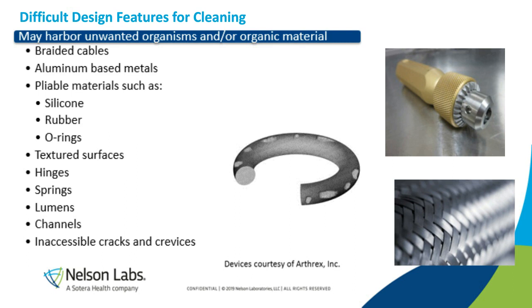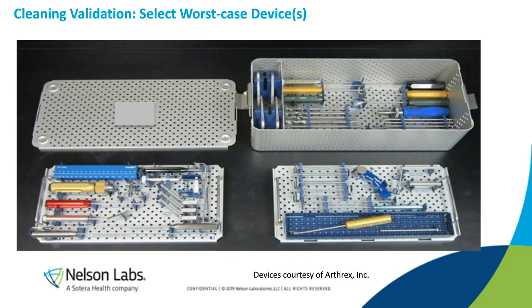Here's an example of how we would choose a worst-case device for a cleaning validation. As you can see, this tray of devices will be used for the same surgical procedure. And now we have to choose the device which has the most challenging features to clean. So if we look at this tray of devices, it's probably kind of hard to see on your screen as there's 4 different levels of devices.